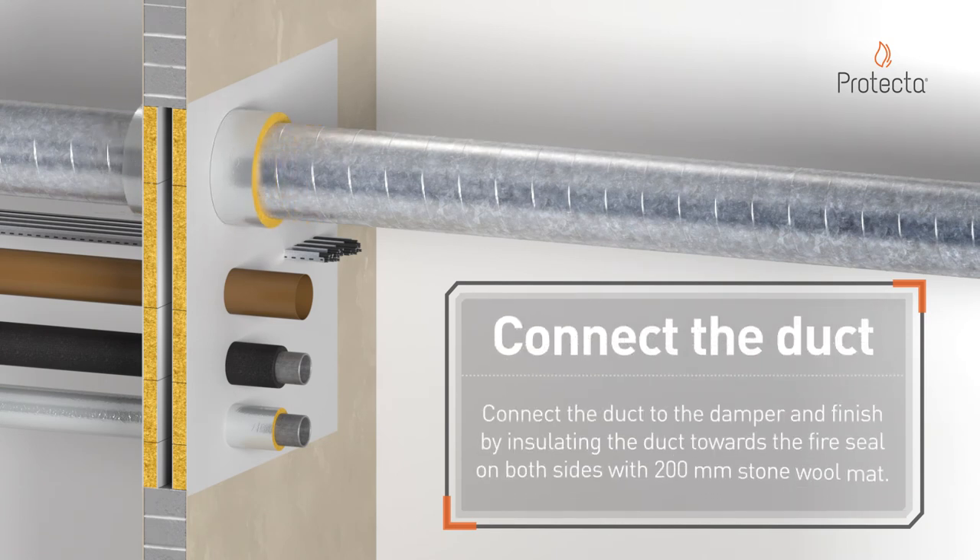Connect the duct to the damper and finish by insulating the duct towards the fire seal on both sides with 200mm stone wool mat.